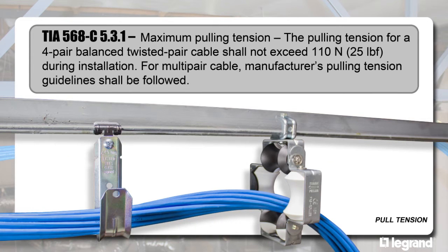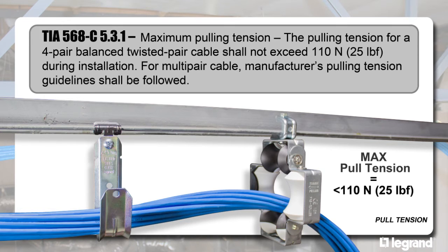The maximum pull tension should not exceed 25 pounds during installation to prevent damage to the cable. It is also best to use a cable pulley when pulling cable through tight bends.